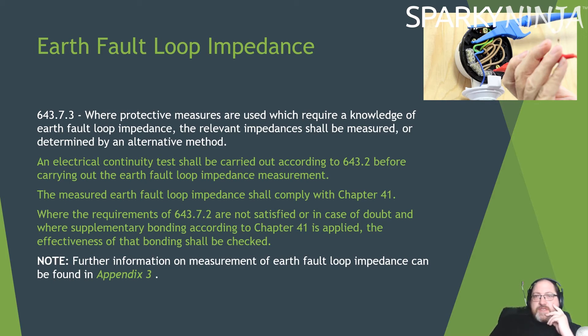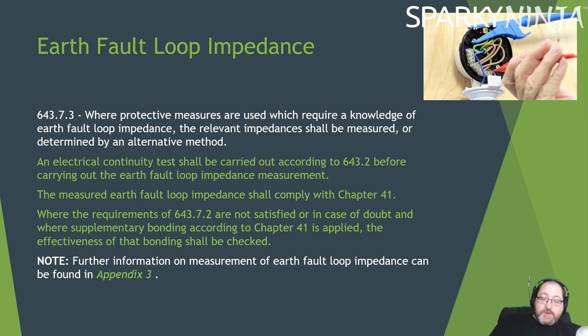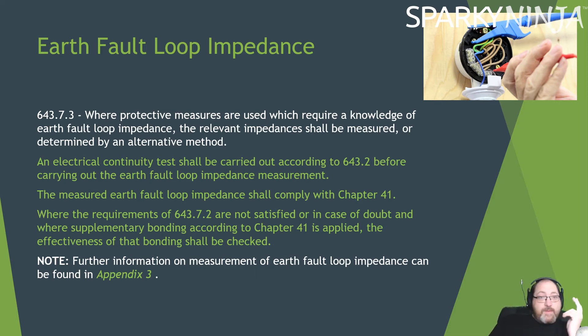An electrical continuity test will be carried out according to 643.2 before carrying out an earth fault loop impedance measurement. The measured earth fault loop impedance will comply with Chapter 41, and if it is not satisfied — in case of doubt where supplementary bonding according to Chapter 41 is applied — the effectiveness of the bonding shall be checked. So you measure continuity before your earth fault loop. Also note: further information on the measurement of earth fault loop impedance is found in Appendix 3 — it used to be in Appendix 14, it's now in Appendix 3, so that's moved.